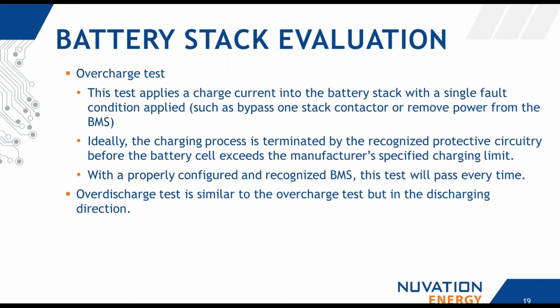So one part of UL 1973 is the overcharge test. This is a test that applies a current to the battery stack with a single fault condition applied. After a construction review of your 1973 stack has been completed, the NRTL reviewer has an idea of where a weakness might lie and the best place to put that single point failure. They may bypass your contactor or just remove power from the BMS, and then they apply the charging process. Ideally, your protective circuitry isn't compromised by a single point failure, so the charging process is just terminated.